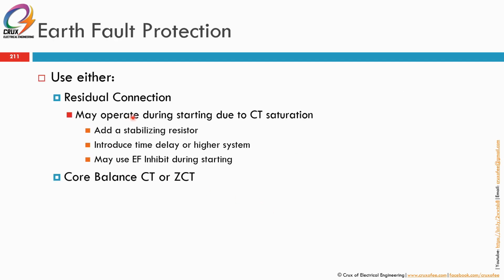For earth fault, there's two types of detecting the earth fault. First, we have the residual connection. The second type is the core balance CT or the zero sequence current transformer, ZCT. For the residual connection, it's normally three phases summation, so it may operate during starting due to CT saturation.